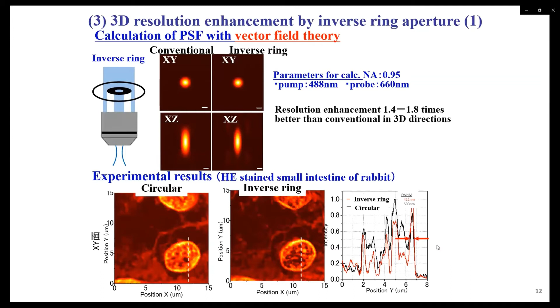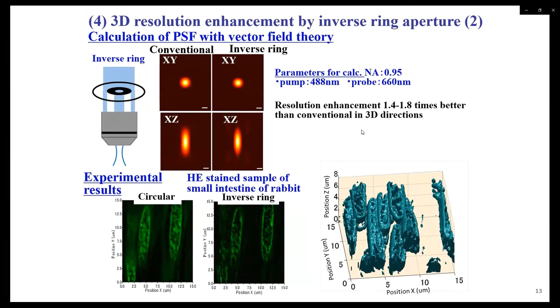Also, we calculated the point spread function utilizing vector field theory. Not only XY but also XZ depth resolution can be enhanced nearly 1.4 to 1.8 times better than the conventional microscope in the 3D direction. And high sensitivity is also obtained by signal-to-noise ratio improvement with the auto balance detection system, ABD.